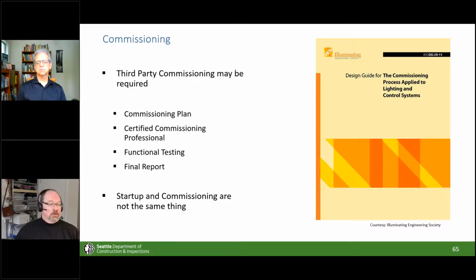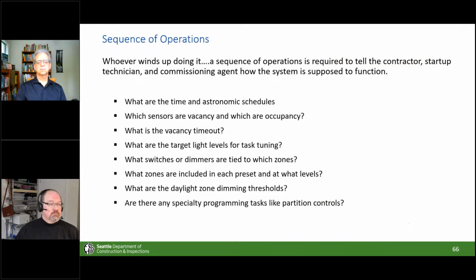If you go to the next one. Ultimately, this cycles back to what I was saying earlier. You need a sequence of operations, right? Somebody is going to need to program all of these things in your control system, and just as importantly, when you're talking about commissioning, somebody's going to need to verify them. So this sequence of operations needs to be available for both the programmer and the third-party commissioning agent.